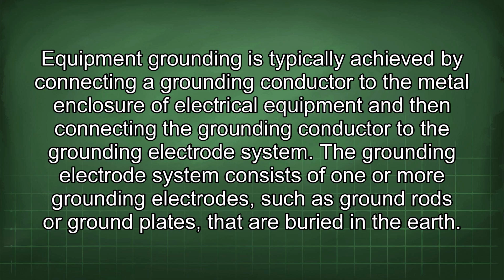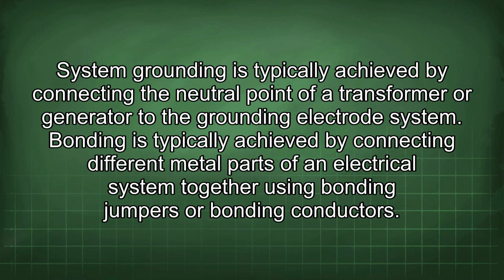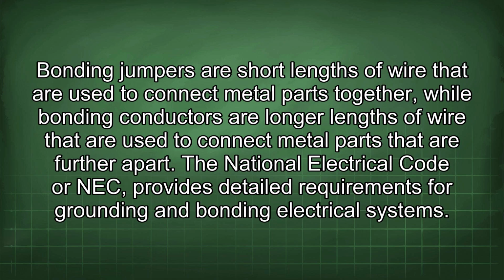The grounding electrode system consists of one or more grounding electrodes, such as ground rods or ground plates, that are buried in the earth. System grounding is typically achieved by connecting the neutral point of a transformer or generator to the grounding electrode system. Bonding is typically achieved by connecting different metal parts of an electrical system together using bonding jumpers or bonding conductors. Bonding jumpers are short lengths of wire that are used to connect metal parts together, while bonding conductors are longer lengths of wire that are used to connect metal parts that are further apart.